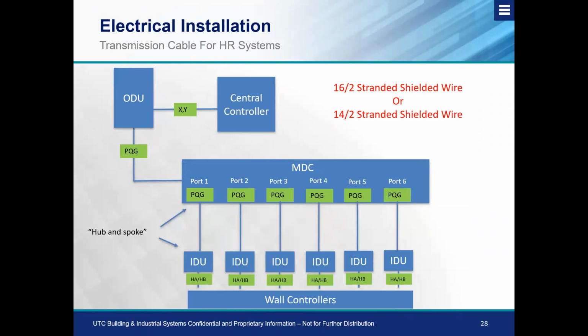And then finally, just covering some advantages before we transition over into the Toshiba carrier side of things. The advantage that we have over the other two pipe systems on the market is what's called hub and spoke. So what we have is our outdoor unit. We have our communication bus that has a small plug that will wire in directly to this MDC and then hardwire in the X and Y terminal on the outdoor unit. If you have a centralized controller, you hook up X and Y. If you don't, you just leave it alone. Always wiring this into PQG.